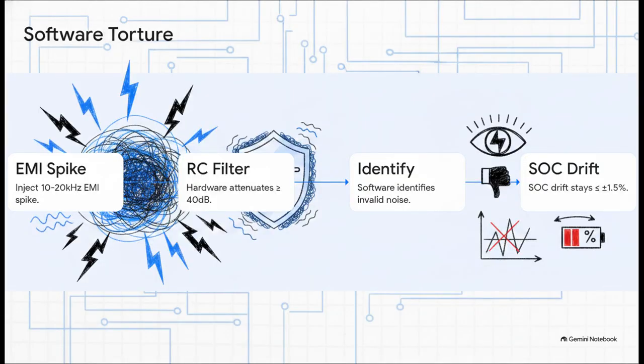Then, if they survive that, comes the software torture test. Engineers intentionally attack the system. They inject a vicious 10 to 20 kilohertz electromagnetic noise spike, simulating the absolute worst-case scenario coming off the vehicle's motor. The hardware RC filter is required to crush that noise by at least 40 decibels right off the bat. Simultaneously, the software must instantly identify the impossible voltage jump, anything greater than 0.5 volts in 10 milliseconds, label it as invalid noise, and just ignore it. And through all this crazy interference, the battery's state of charge calculation cannot drift by more than 1.5%.